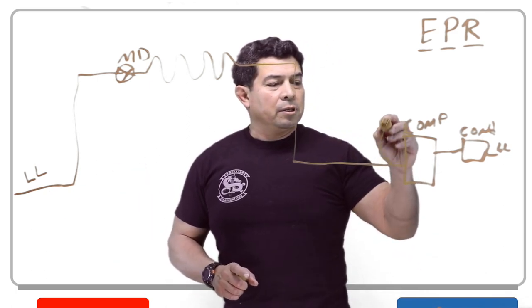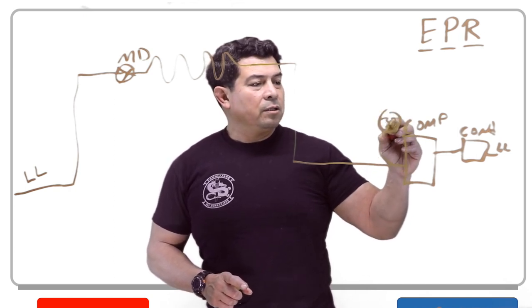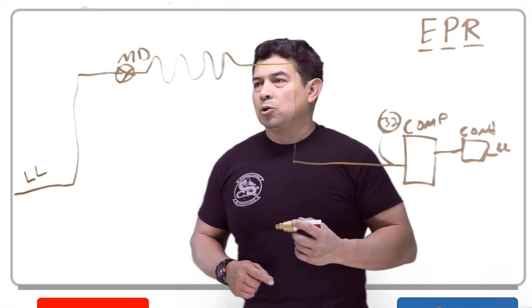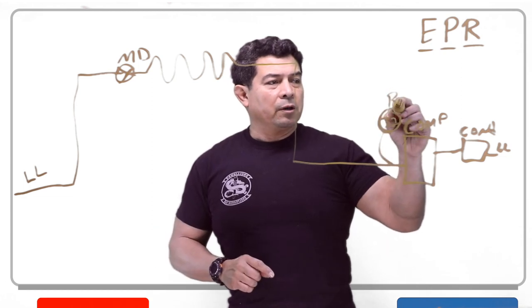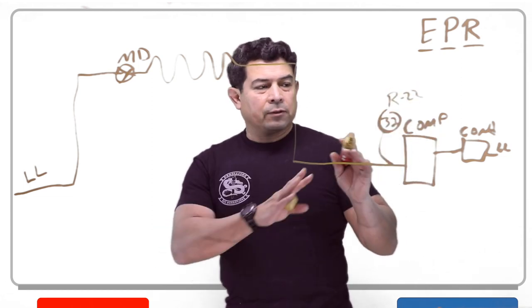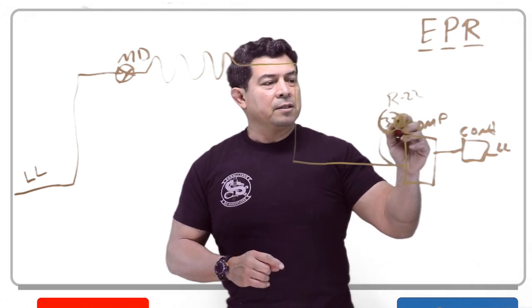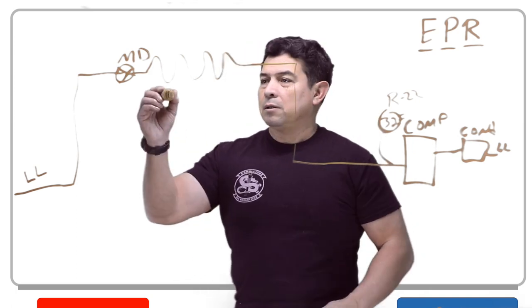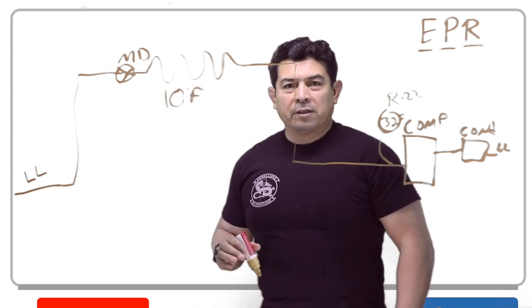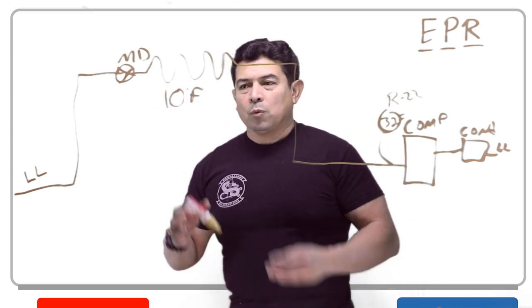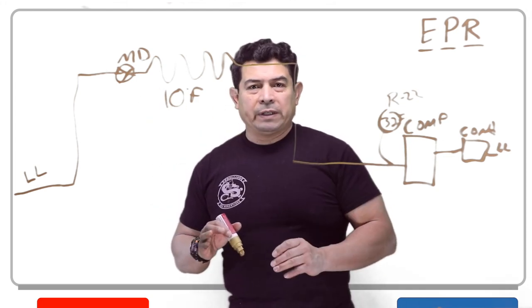Now let's say that this compressor has a suction pressure of 32 PSIG. If this is R22 - I'm talking about R22 here - if it has 32 PSI suction, that means the evaporator is going to be 10 degrees Fahrenheit. Because this is a refrigeration system, we're keeping things very cold in there. So we're maintaining this evaporator at 10 degrees.